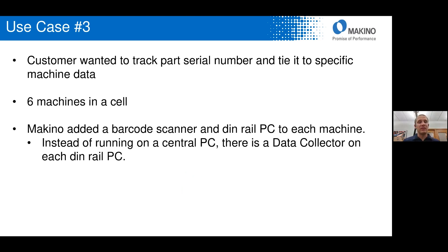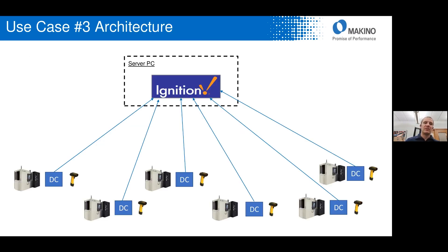The last use case was a customer that wanted to track their part serial number and relate that to specific machine data. They had six Pro5 machines in one cell and requested Makino add a barcode scanner to collect the part serial number. Instead of running on a central PC, we added a DIN rail PC to each machine where we could tie in the barcode scanner with the Data Collector. The Data Collector and barcode scanner run inside the machine control on that DIN rail PC, collect the data, and publish it via MQTT to a central server PC running Ignition. This allowed the customer to build their own database and track the serial number of the part with all of their feeds, speeds, overrides, and alarm information.